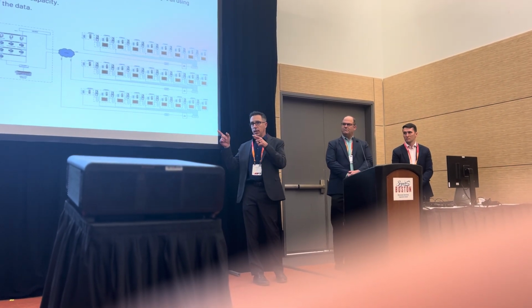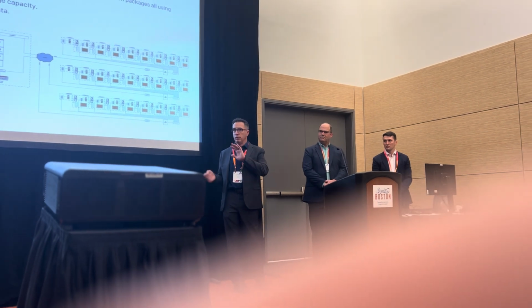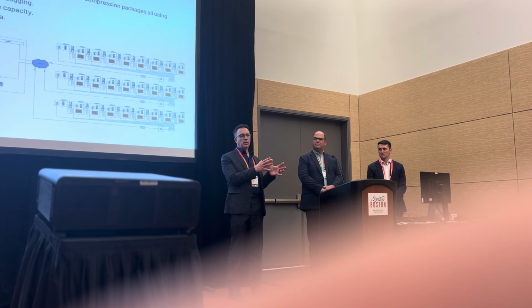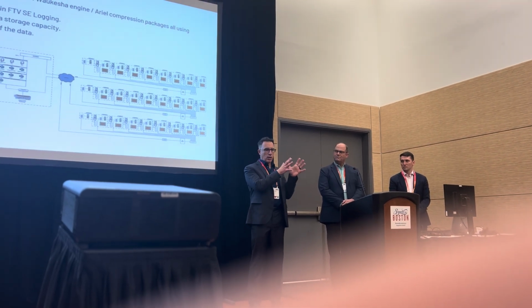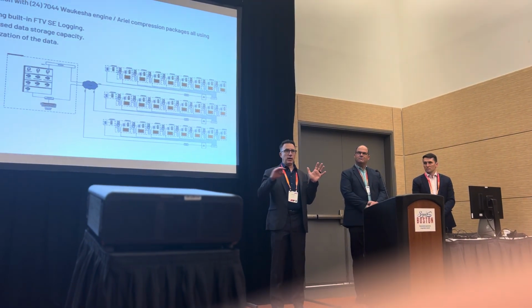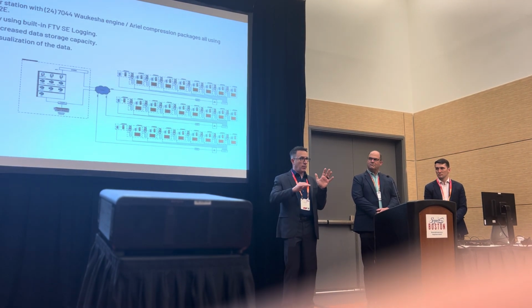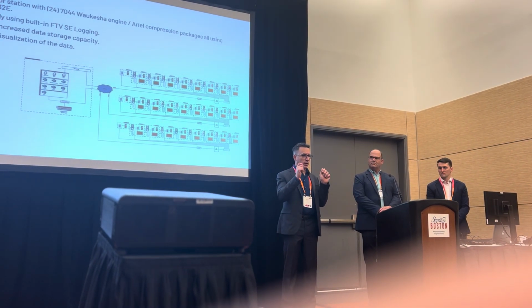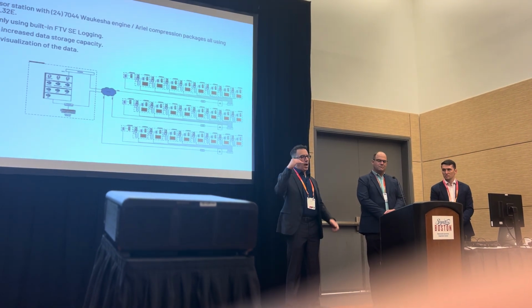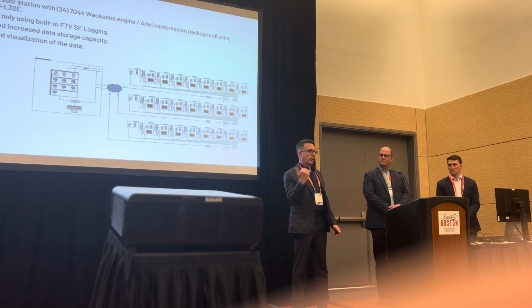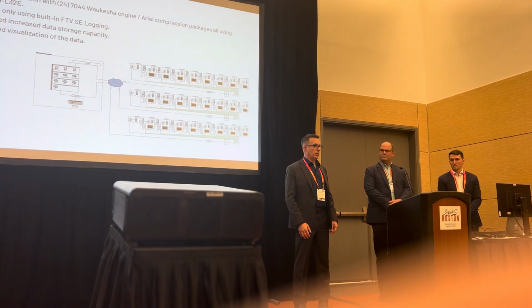No matter if they picked up 20 more locations, it might be a completely different protocol set. But using edge compute and the applications that are available to us, it's coming out, and one of the things that we did is a unified namespace. It's coming out in that one way. So if I go to site A, B, and C, I know that this valve is going to have the same naming convention, so I can put it in the SCADA historian, etc.